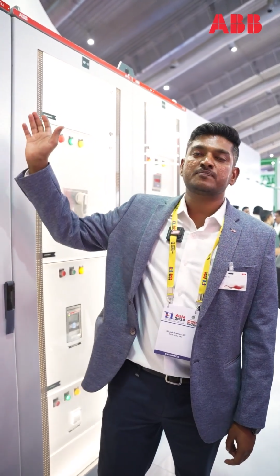Above this panel, we have a flap. Whenever an internal arc occurs, the flap is going to open. It is a kind of pressure cooker concept we have used. When an internal arc occurs, the arc is not going to flush out in front of the panel. It is going to go up, over the panel.